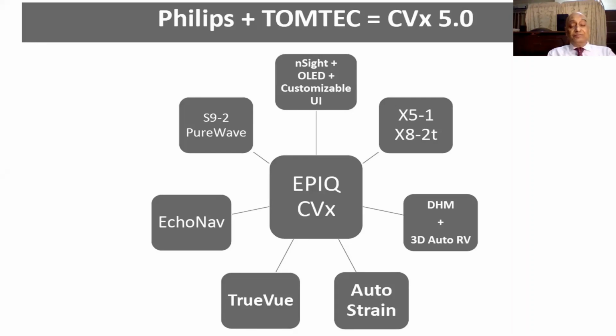The screen is thinner and has better resolution, because the resolution not only depends on your imaging probes or the expertise in the use, but also on the monitor. So if you have an excellent monitor like the OLED monitor, the resolution automatically improves. And with the max view that is available, both in EPIQ 7C and in EPIQ CVx, you can get a very large image occupying the entire screen without any change in the resolution. Normally, when you go to a larger screen, you tend to lose resolution, but here the resolution is maintained or even improved. Then you have the technology that has come up, which is called PureWave technology in the transducers, which I'll explain.